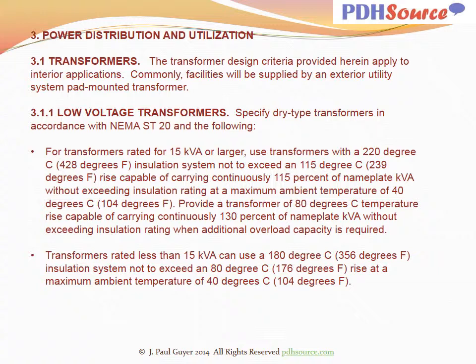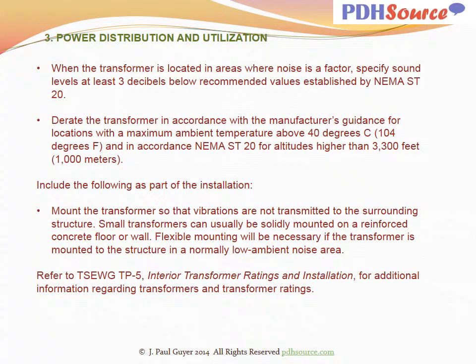Provide a transformer of 80 degrees centigrade temperature rise capable of carrying continuously 130% of nameplate kVA without exceeding insulation rating when additional overload capacity is required. Transformers rated less than 15 kVA can use a 180 degrees centigrade, 356 degrees Fahrenheit insulation system, not to exceed an 80 degrees centigrade, 176 degrees Fahrenheit rise at a maximum ambient temperature of 40 degrees centigrade, 104 degrees Fahrenheit. When the transformer is located in areas where noise is a factor, specify sound levels at least 3 decibels below recommended values established by NEMA ST20.